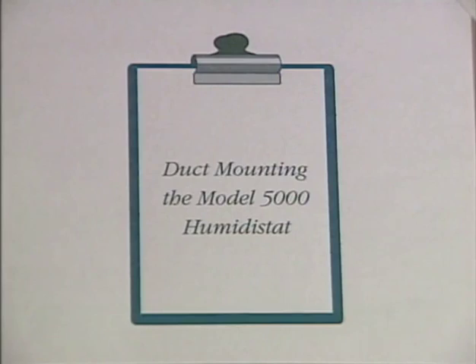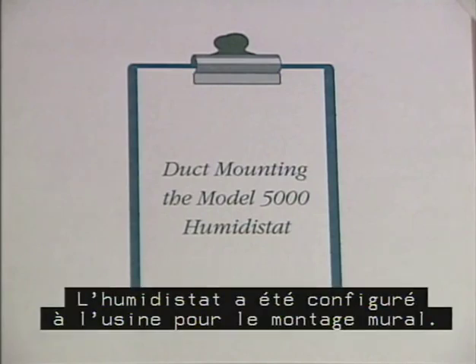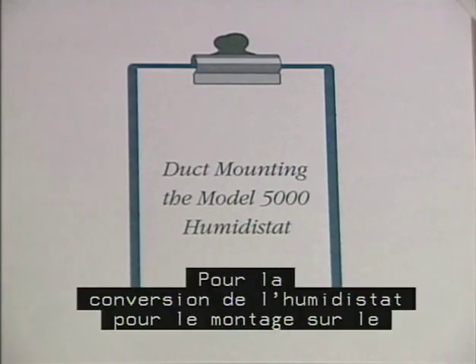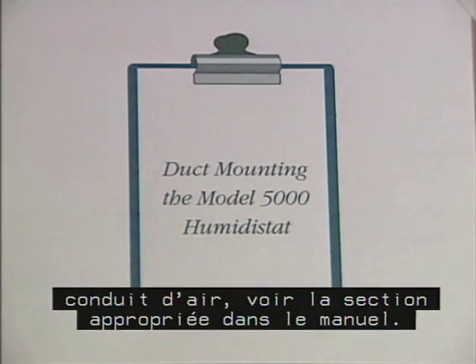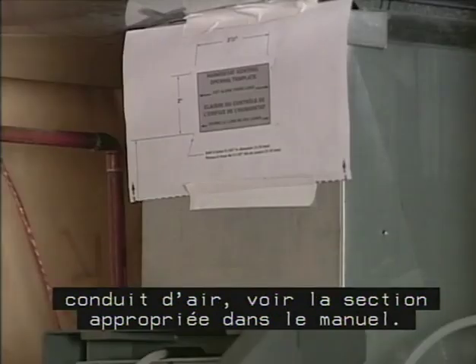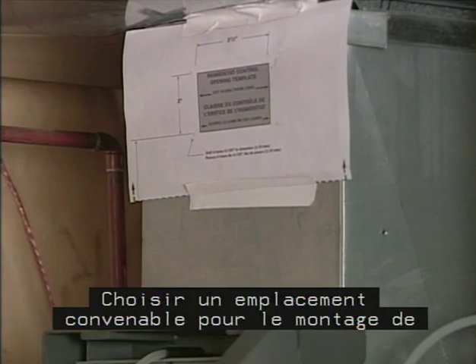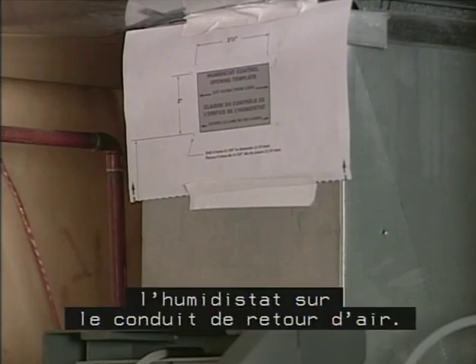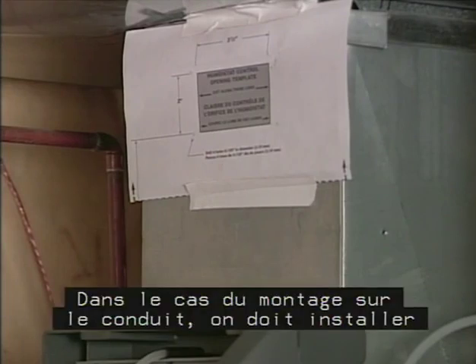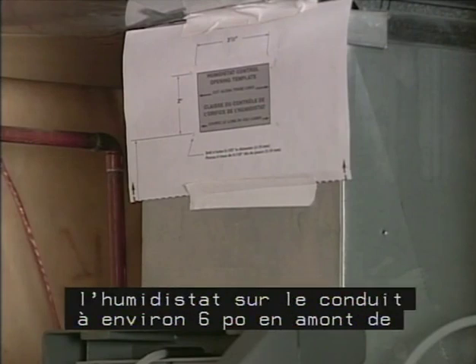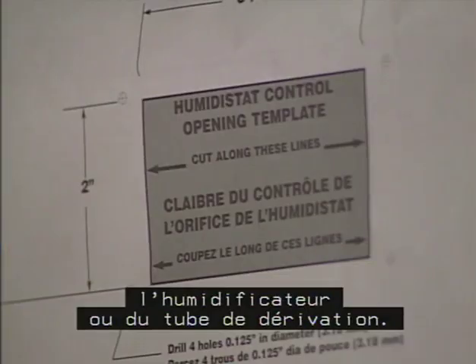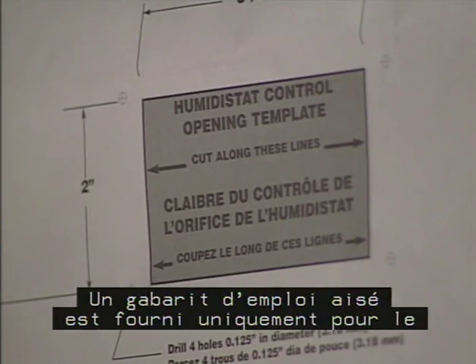The humidistat is packaged at the factory ready for wall mounting. Refer to the appropriate section in the manual to convert the humidistat for duct mounting. Select a convenient location to mount the humidistat on the return duct. When duct mounting, the humidistat must be located on the return duct about 6 inches upstream from the humidifier bypass tube. The unit comes with an easy-to-follow humidistat mounting template.